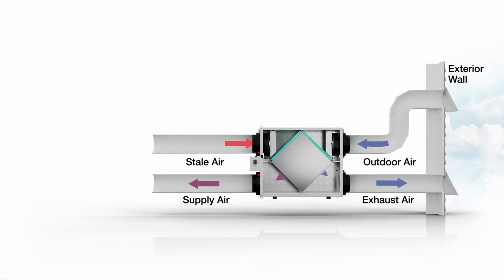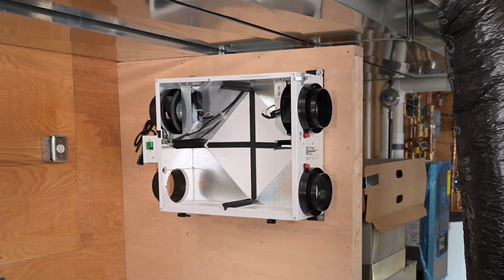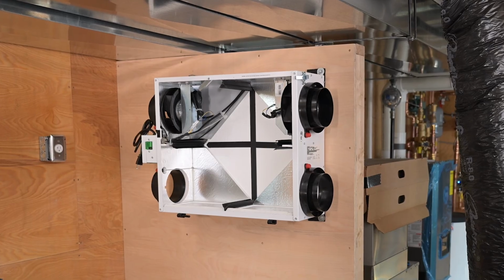Lastly, the fully dedicated installation is a standalone system where the ERV draws stale air from specific points and delivers fresh air to specific locations. This system is not connected to the air handler or furnace, making it ideal for installations that don't have a central HVAC system. For all installation scenarios, here are a few tips to maximize your airflow.